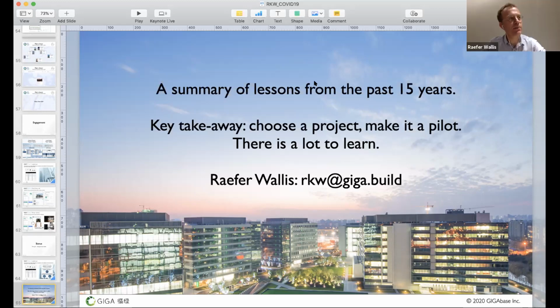Older buildings are actually my favorite because they're the biggest challenge. In many cases, it's older buildings where there's just no capacity to increase air volume—the fan is running near maximum, or increasing fan speed would destroy acoustics and create far too much noise. So classic interventions like replacing those with a fan grid, and now there are IoT-based fan grids, come into play.